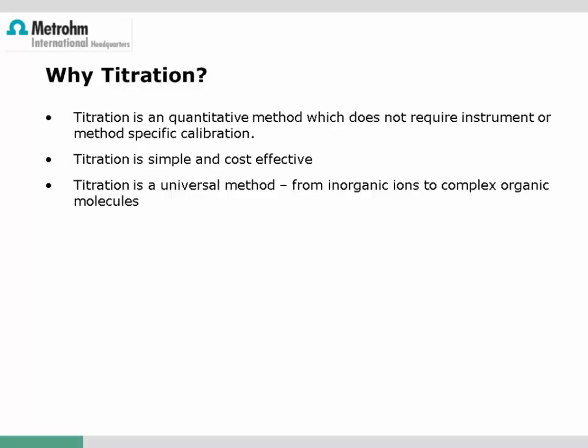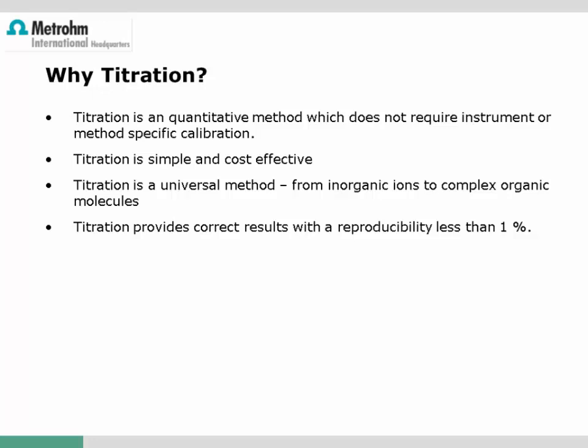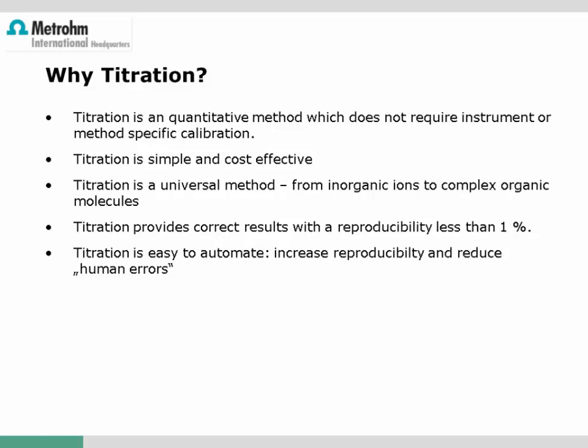Titration is also a very universal method. A titrator can be equipped for the determination of various species, from inorganic ions to complex molecules. Reproducibility is usually below 1%, but in many applications even less than 0.3% can be achieved. The performance of the titration system can be further enhanced when automation for liquid handling or sample preparation steps is used.